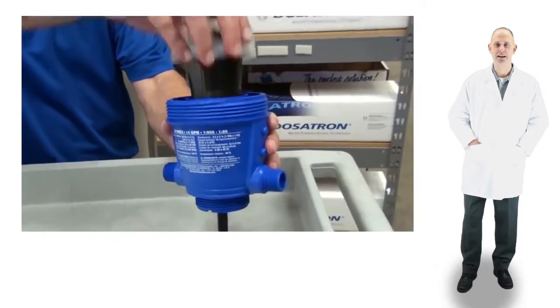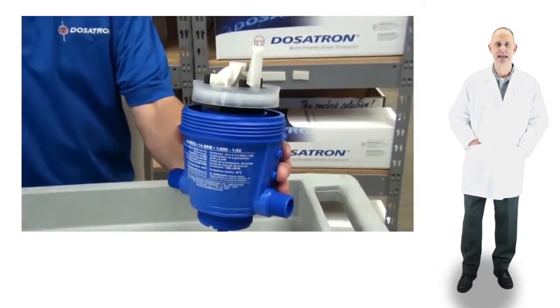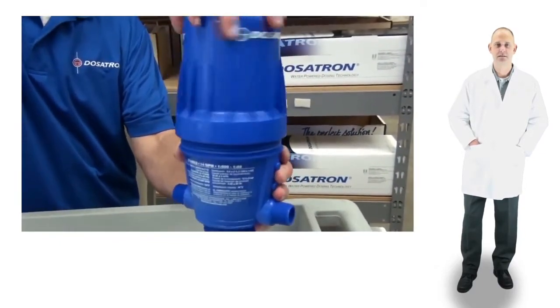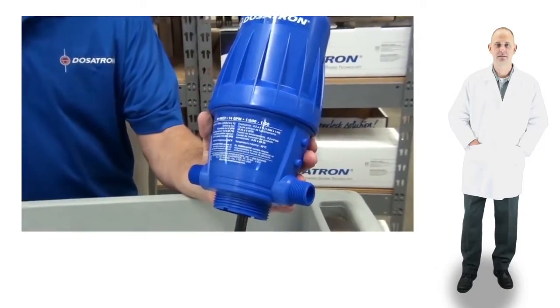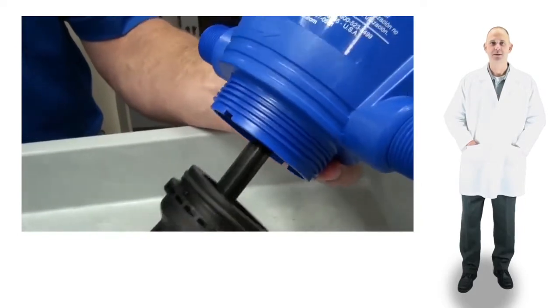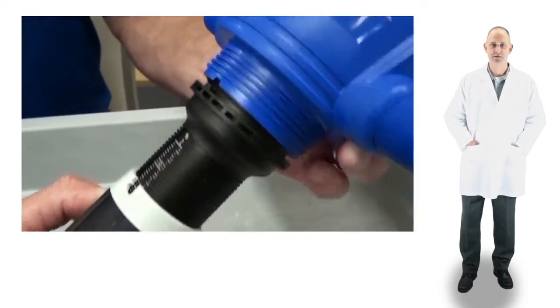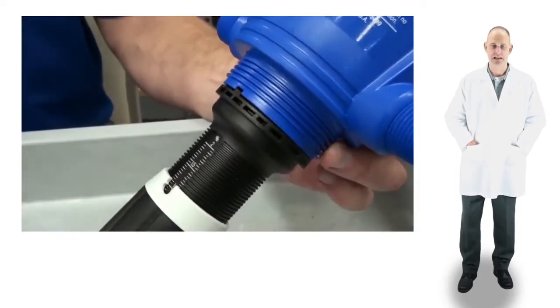Insert the piston into the body and replace the bell housing, hand tight. Align the notches in the lower part of the body with the teeth on the top of the injection stem assembly and reinstall the nut hand tight.